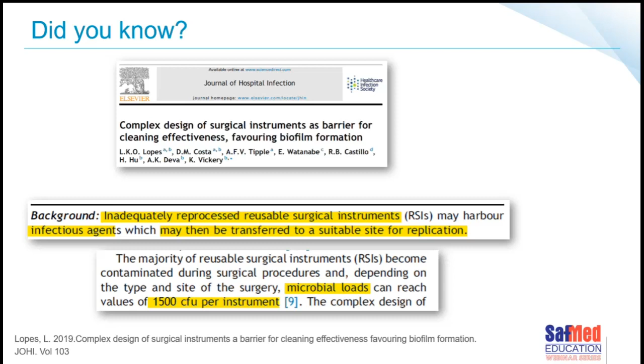So what the authors did over here was they decided they were going to look at reprocessing these devices. They took 20 of these loan set type devices, so flexible reamers and depth gauges, and they purposefully inoculated them with a broth of sheep's blood and microorganisms. Now when a manufacturer actually makes an instrument, they have to do this anyway. They have to do this process to prove to you that if you follow all the correct cleaning steps and the reprocessing steps that they've given you, the device will turn out to be sterile.